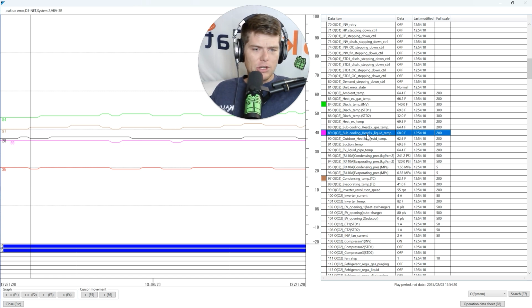Subcooling 14 degrees, a little bit high, 11 degrees plus or minus 3. It's in range. 60 degree discharge superheat, also in the 60s, in range. There's no problem in this data set. And I would love to just take this data set and just hit you over the head with it because there is a problem in this system, but you can't determine that in 26 minutes of freaking runtime data.